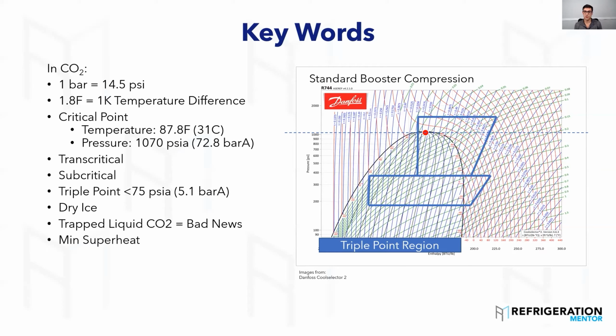Does anyone know what the minimum superheat for medium temp would be? 35 degrees. Yeah, 35, 36 degrees or 20K. Sorry, medium temp we were talking about, we said 36. No, it's not 36 for medium temp. That is low temp. Medium temp is 18, 10K. Low temp's 36. So that was my mistake.